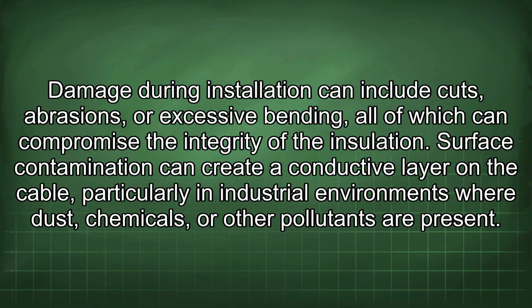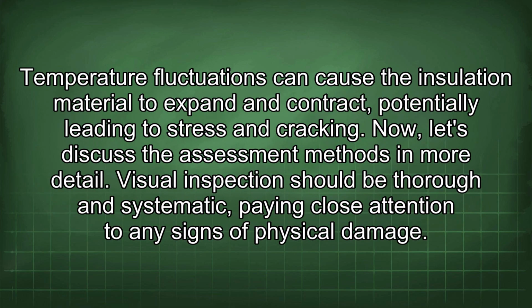Surface contamination can create a conductive layer on the cable, particularly in industrial environments where dust, chemicals, or other pollutants are present. Temperature fluctuations can cause the insulation material to expand and contract, potentially leading to stress and cracking. Now, let's discuss the assessment methods in more detail. Visual inspection should be thorough and systematic, paying close attention to any signs of physical damage.